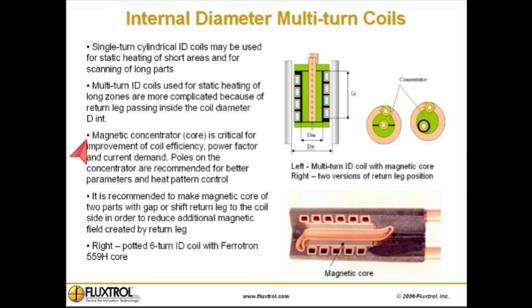Poles on the concentrator are recommended for better parameters and heat pattern control. It is recommended to make the magnetic core of two parts with a gap, or to shift the return leg to the coil side, in order to reduce the additional magnetic field created by the return leg. To the right, we see a potted six-turn ID coil with a Ferrotron 559H core.